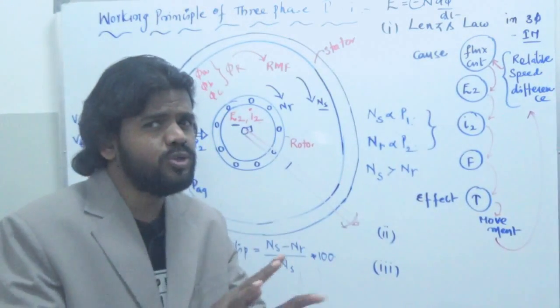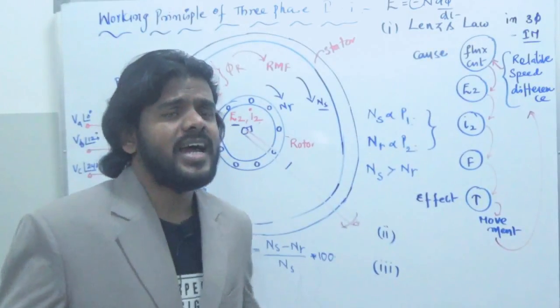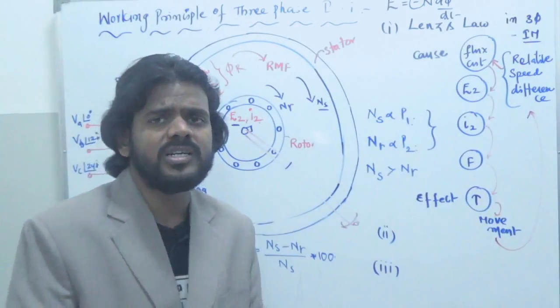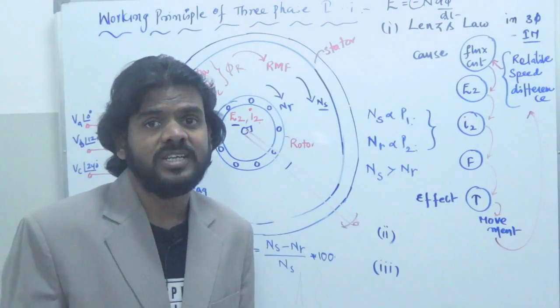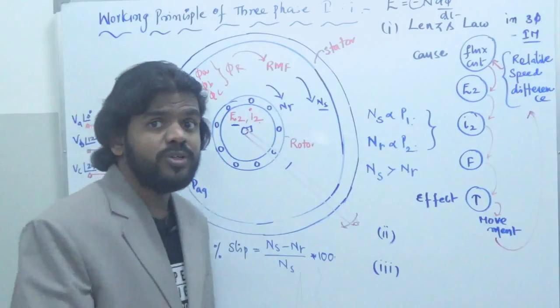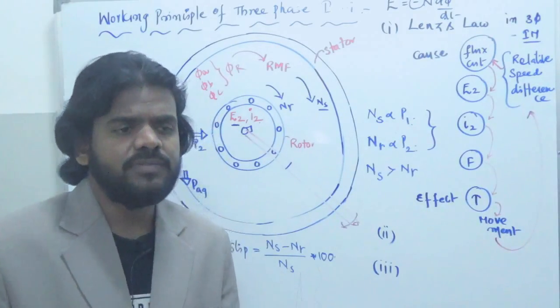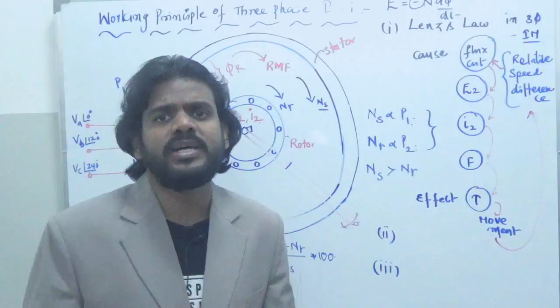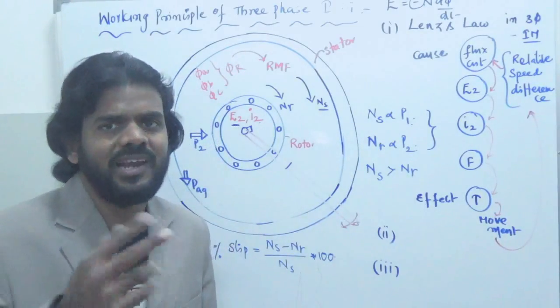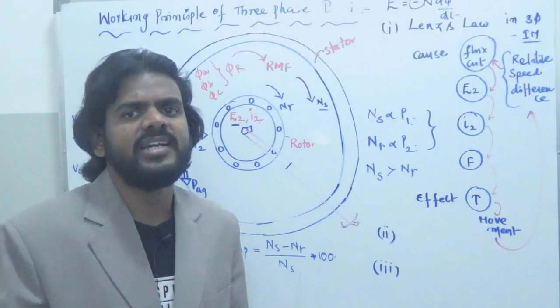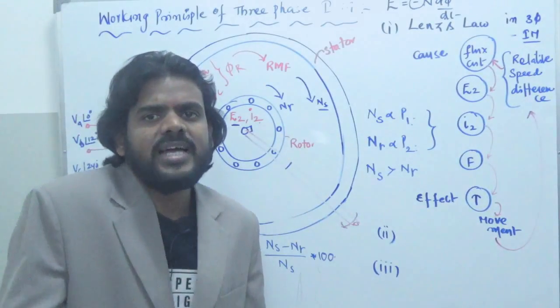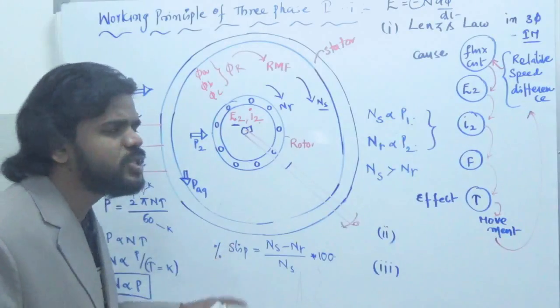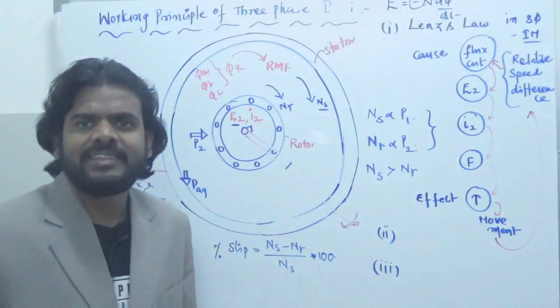The reason we have slip is that the rotor always slips behind the stator. In a synchronous motor, the rotor always runs at synchronous speed, so there is only one speed and no slip. In DC motors — series, shunt, or any type — there is also only one speed. The induction motor is the only motor with two speeds, Ns and Nr, making slip a unique and important concept here.